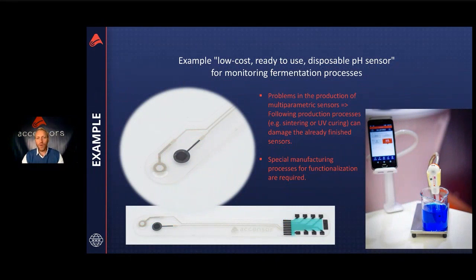One example, also from the other side, from the production side, the idea behind the SMD Foilsensors and especially the biosensors. Here you see a pH sensor system. A pH sensor system is built up from 2 electrodes. The silver electrode is the reference electrode, and the gray or black electrode is the pH sensitive electrode. And you do an potentiometric measurement between both electrodes, because the pH sensitive electrode will change its potential if the pH value is changing in the medium, and the reference electrode will not change its potential, because it has a stable potential in this liquid.